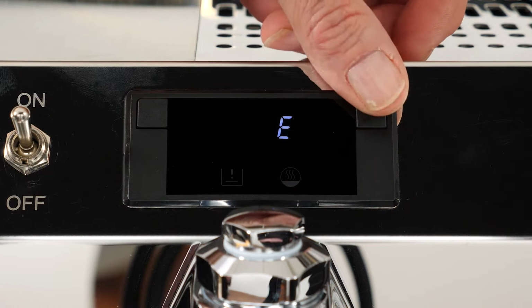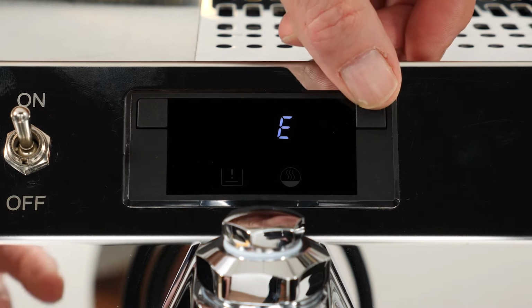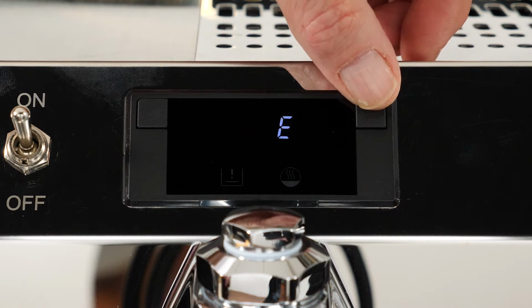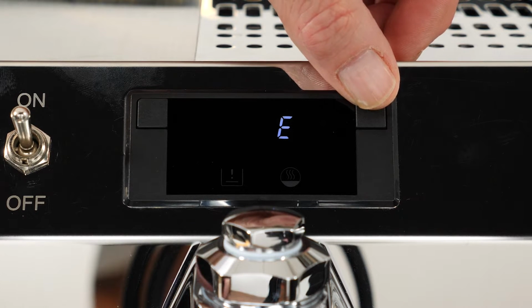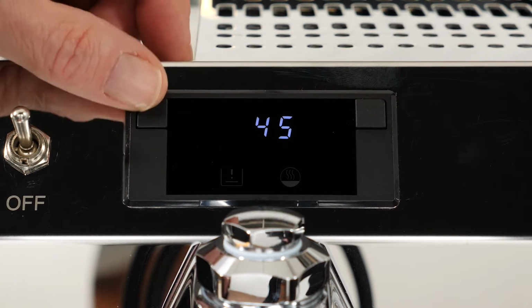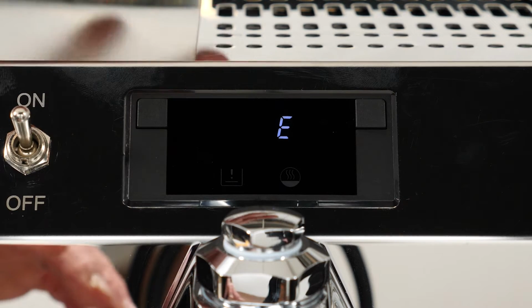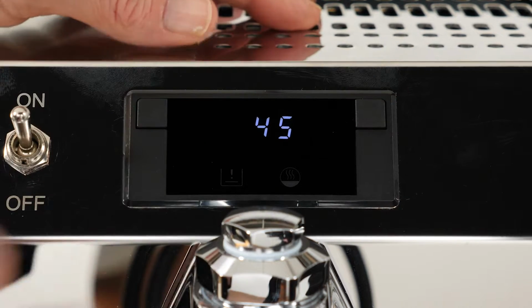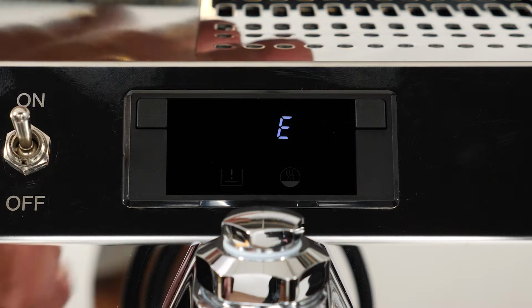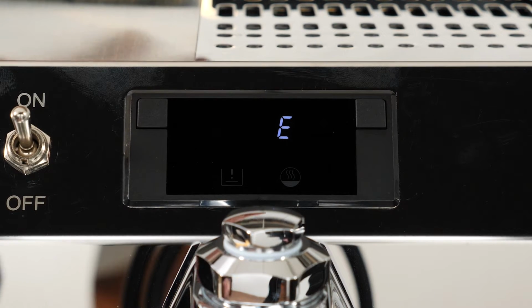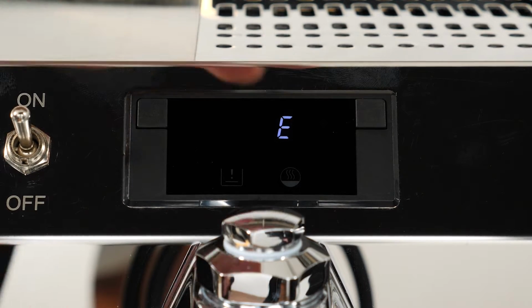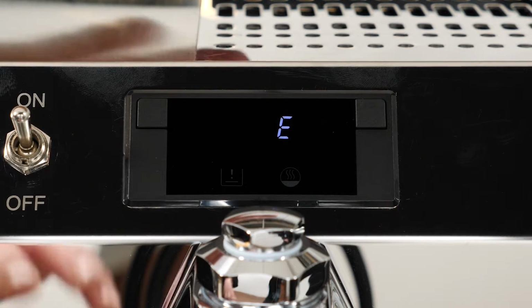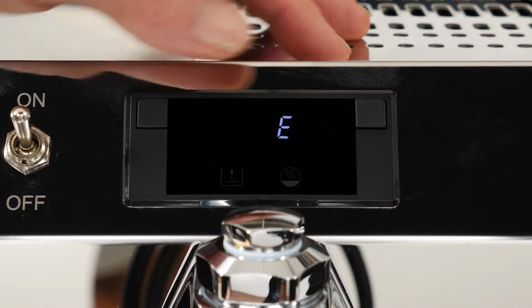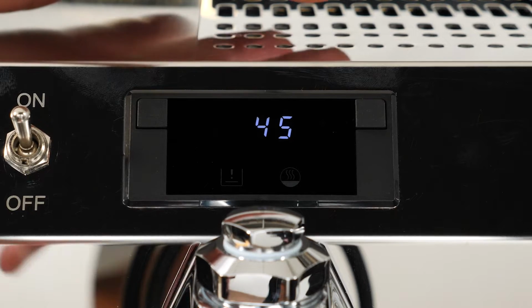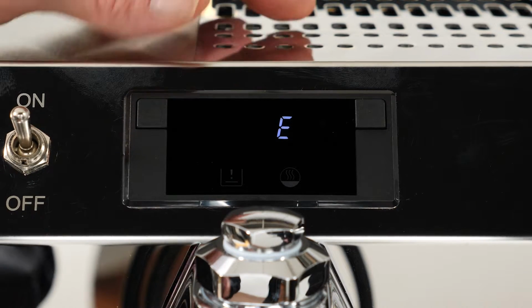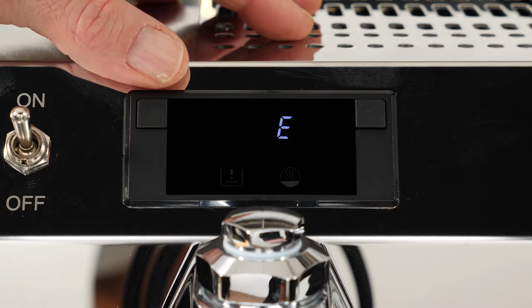This is the offset I mentioned up front. On this machine, when you set the temperature in the PID, it's going to be 45 degrees—the offset comes set at 45 degrees. That means the water in the boiler is 45 degrees hotter than what you get at the group. We've done a lot of testing and found that's about right, so when you set a brew temperature on this machine, you're always subtracting 45 degrees. There may be cases where you'd change this in a very hot or very cold environment, but really it's best to leave it alone.